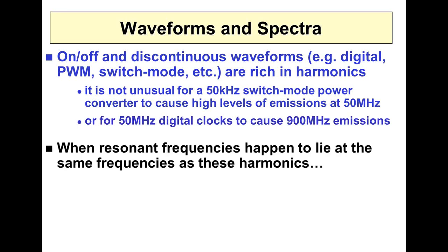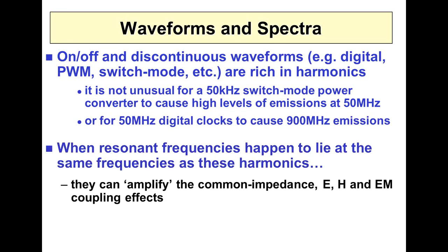The problem is specifically when we have resonances — in other words, accidental antennas — that lie at the same frequencies or close to these harmonics. Then we get the common impedance and electric-magnetic coupling effect, amplified maybe 20, 30, 40, 50 dBs. So this is where many of our problems arise.